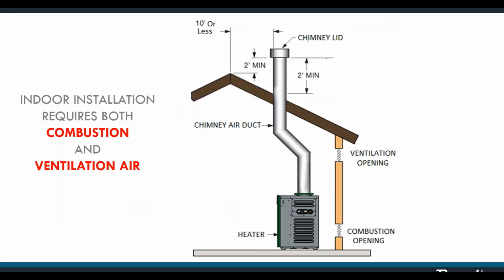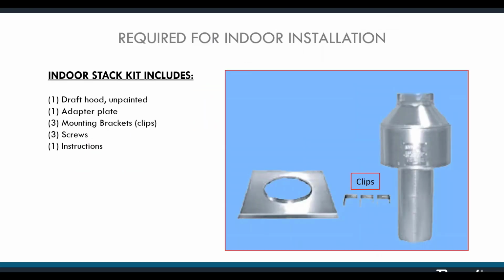Indoor installation has certain requirements for air. The heater needs both combustion and ventilation air. You can't have a fire without air. That air must be provided through an opening at the bottom of the wall, down there where it says combustion opening. All right, so as the heater burns, hot exhaust is created, which is vented from the room through a vent duct. The gases rise by convection, creating a pull or a draft. Now, this creates negative pressure within the vent, causing combustion air to be pulled in too quickly and disrupting the flame, causing problems. The most notable problem would be soot. All right, we can fix that.